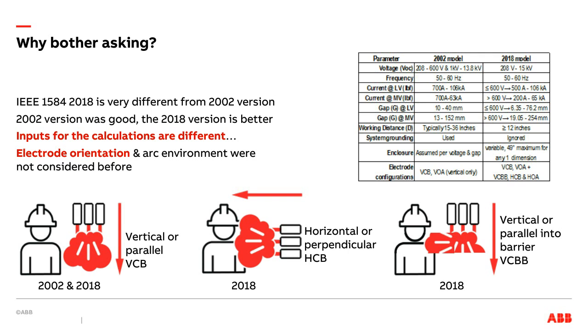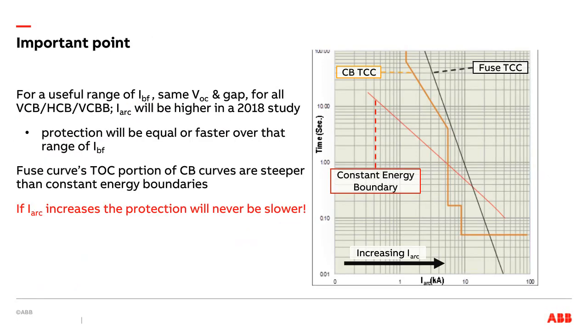Because if you have a much larger gap, then your arcing current could be significantly lower. And if it's significantly lower, what I said about the protective device before no longer applies, now the potential is that your protective device is actually slower. And then we go back to that chart. Your big issue is if you suddenly move from this protection here to that protection there. That's a huge difference in time, and time is a big variable. It's an important variable. Same with a fuse. If I'm moving from the right to the left, a fuse curve is pretty steep. It doesn't take an awful lot of shift in arcing current before that fuse is protecting quite a bit slower. Another consideration with fuses, but we're not going to get into now.